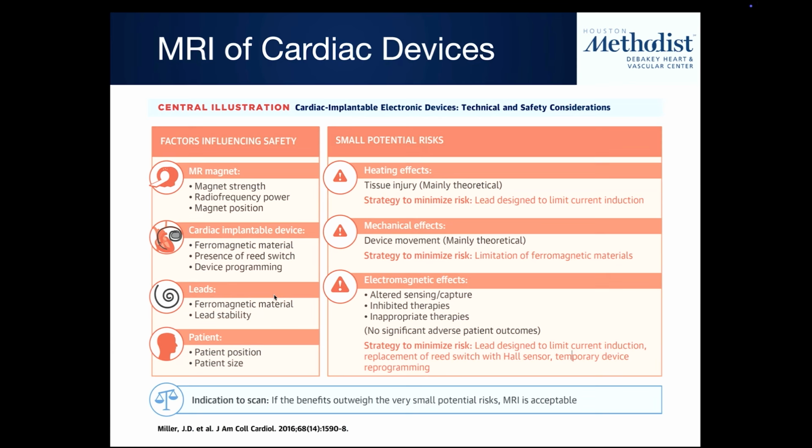We'll go through and figure out, can we manage to do this? Nowadays, we've developed an approach where almost all implanted cardiac devices we can do. But we need to know about it first, so we can say, okay, let's understand what this device is, where it is positioned, and then we modify the way that we do the acquisition, both from the standpoint of reducing artifacts from the device, but more importantly from maximizing safety, okay?